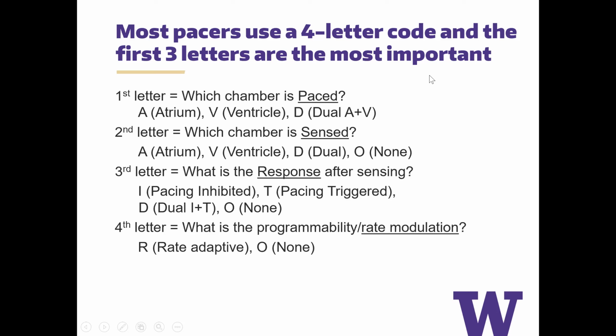So if you do that, you can try to pinpoint, is there something wrong with, for instance, those coaxial leads that I showed earlier? Is there something wrong with the inner insulation, or is there something wrong with the outer insulation? And I think that's what most people think of using unipolar configuration for. There are also some instances where you can get stimulation of muscle when the person is programmed a certain way, and again, having the ability to change those configurations can be useful when you try to troubleshoot that.